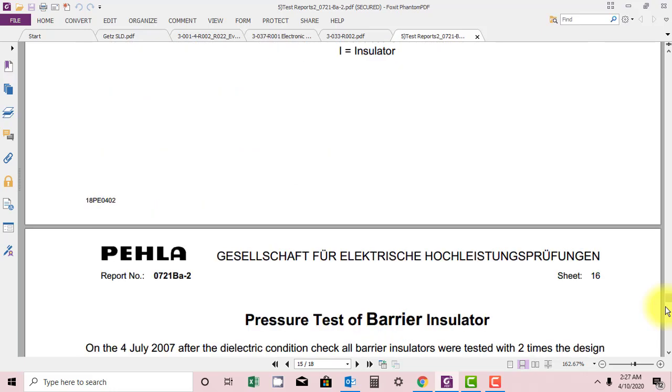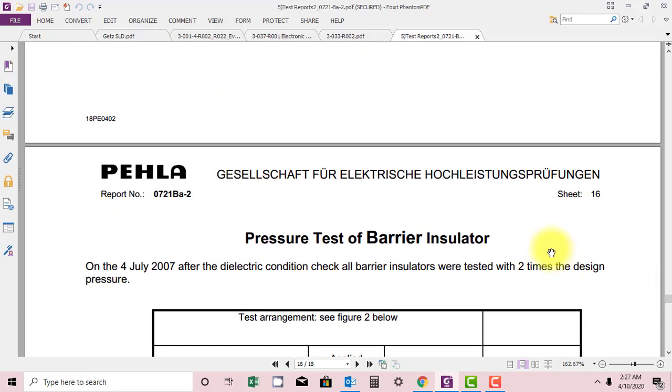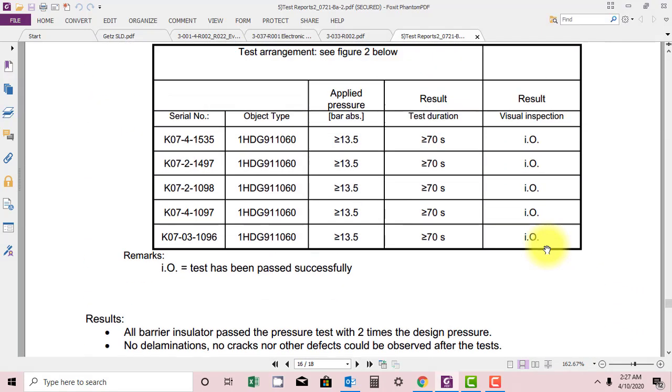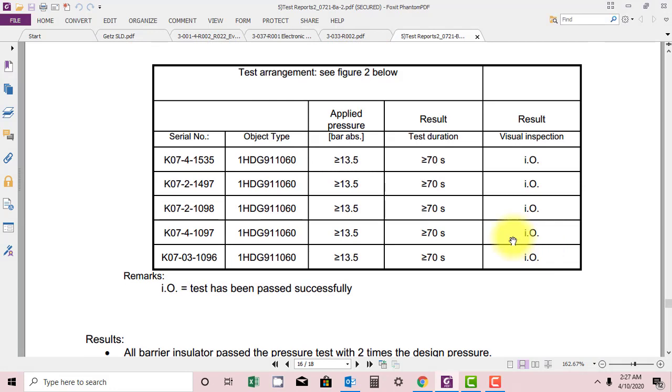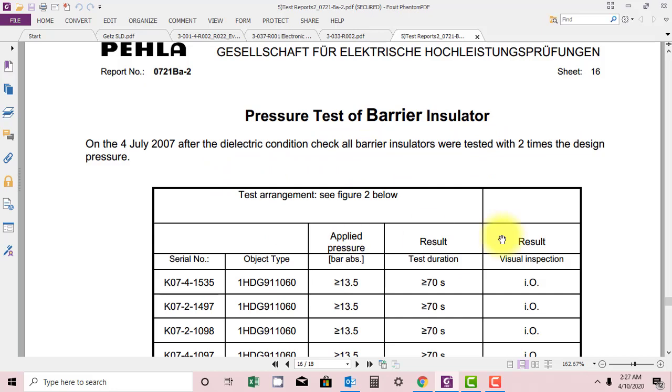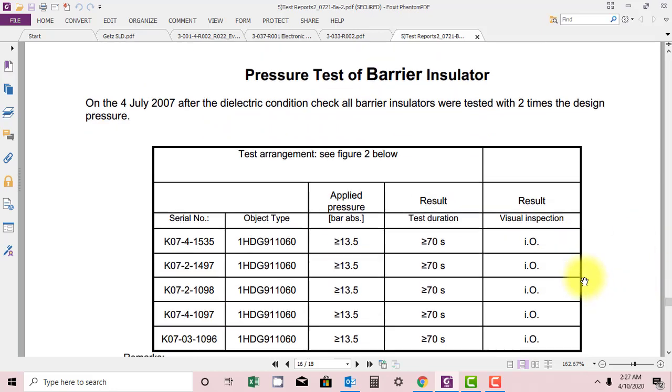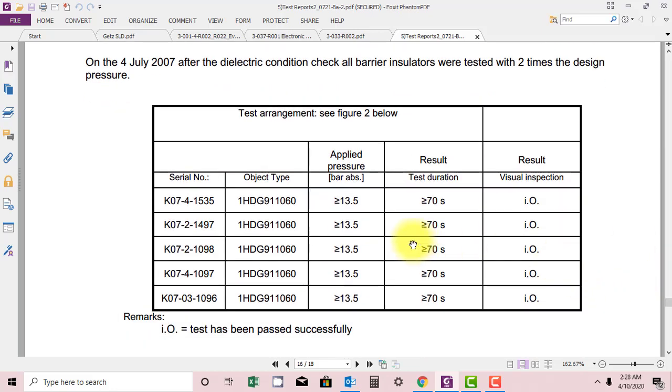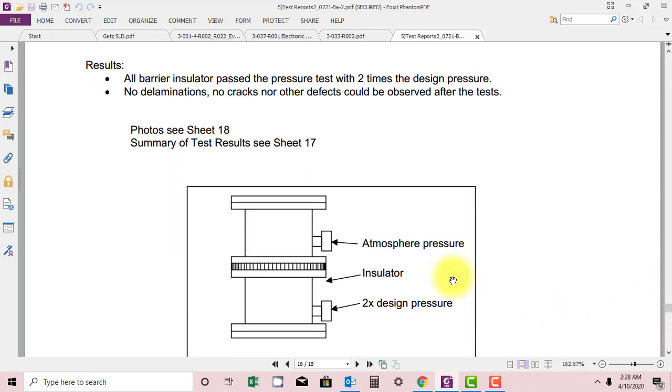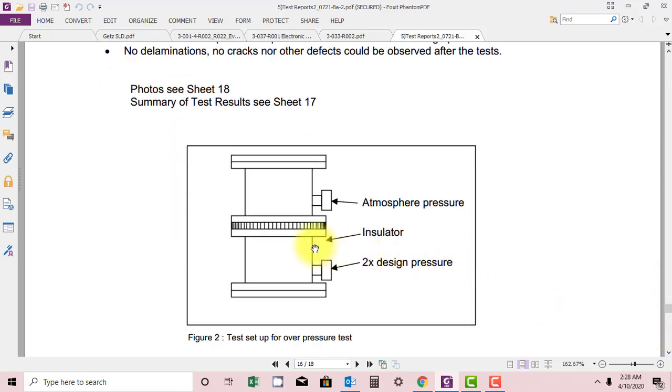Pressure test for barrier insulator: they have applied some bars and the test should stand for greater than or equal to 70 seconds. After dielectric condition check, all barrier insulators are tested with two times design pressure. So design pressure is 6 to 7 bars, so they have applied 13.5 bars.